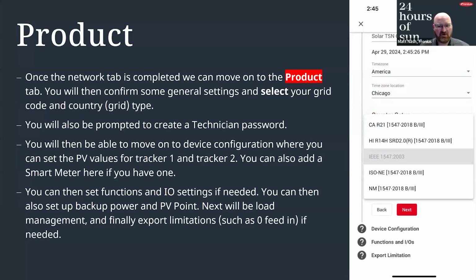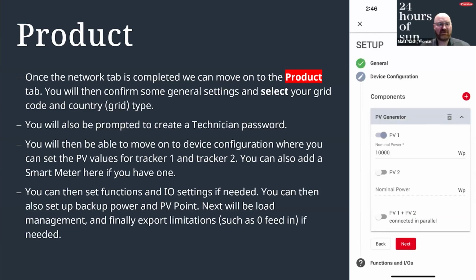Next, then your grid code. So we have multiple grid codes with more coming available as utilities require different settings. Out of the box, we have the California Rule 21 setting. We have the Hawaii Rule 14. We have the standard 2003. We also have one for a standard 2018 1547, ISO New England, and New Mexico. So there are plenty of different options to select from. And then from there, you will actually input all of the things that are connected to the inverter. So the size of the array that the inverter is going to get fed.